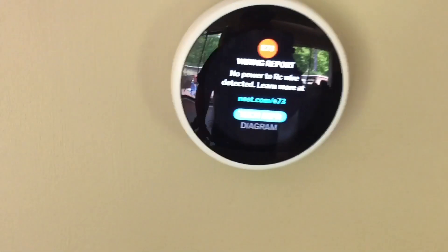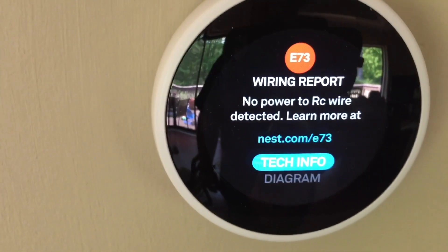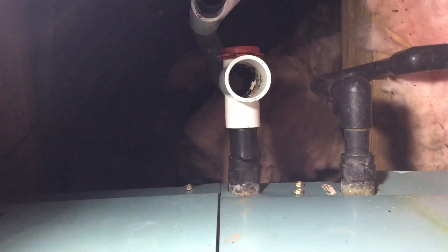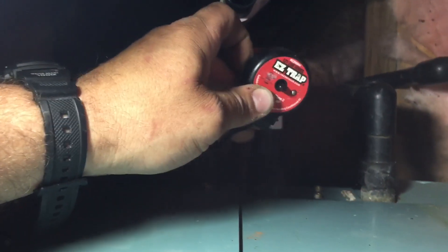It's a NAVAC machine. Okay, here we have a 24-volt EZ Trap, which is to prevent water from overflowing into a customer's ceiling. So it killed power at the Nest, the RC control.